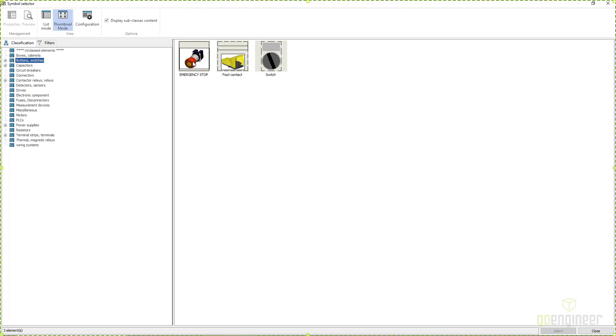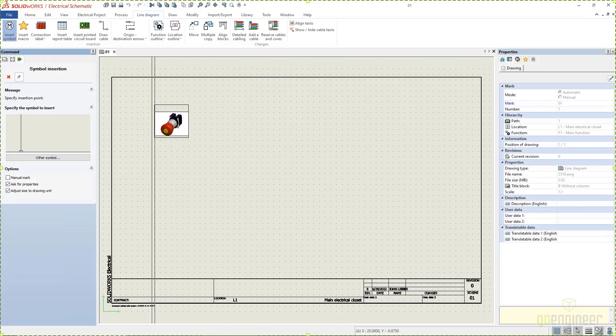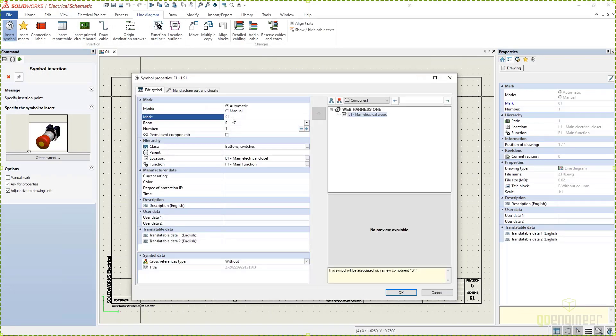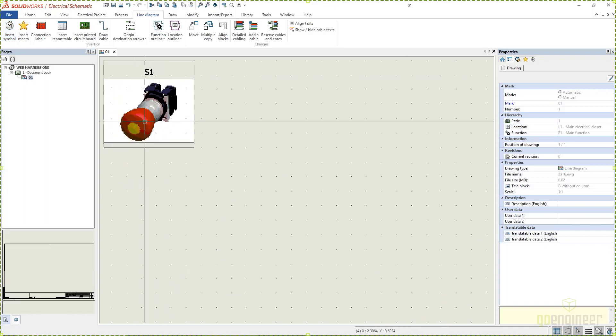So that's the first tip — when you're working inside of SOLIDWORKS Electrical, we do provide a huge library of components and symbols. While I'd love to say we'll provide you with every symbol you could ever want, that would be misleading. In this particular case, I wanted an emergency stop button, I didn't have one, so I created one. I just used the power of SOLIDWORKS — opened a 3D model, rotated it around, I didn't have to ask anybody to draw it. Because if I do a Google search it might be in the wrong orientation. So use the power of SOLIDWORKS, just do a screenshot, bring this guy in, and then I can place that here. It's still going to bring up my properties — it's a switch, it became switch one — and when I click OK you'll see here's my brand new symbol with my e-stop.